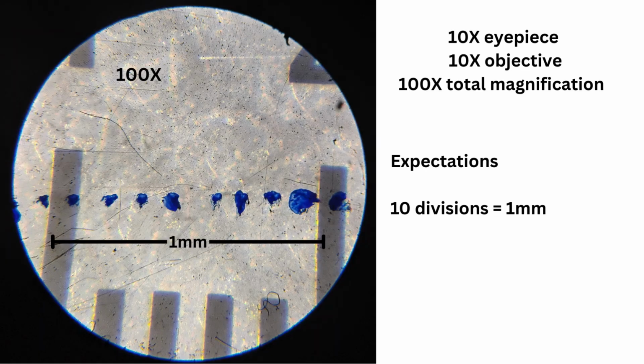To calibrate, I placed the stage micrometer instead of the slide on the stage, and I took images of the graticule with the stage micrometer. If you don't have a stage micrometer, you can think of placing a graph paper and lights from top. It should certainly work up to 100x or 150x. So here's what I found.